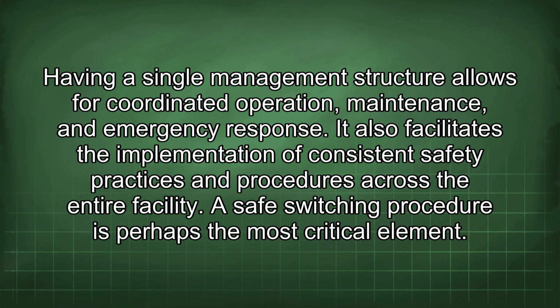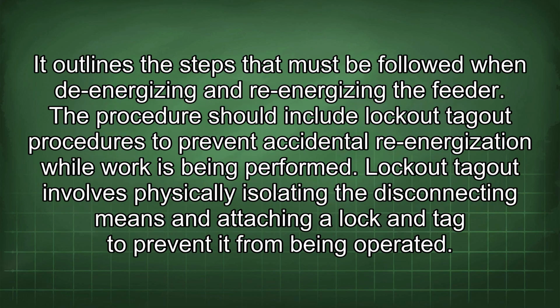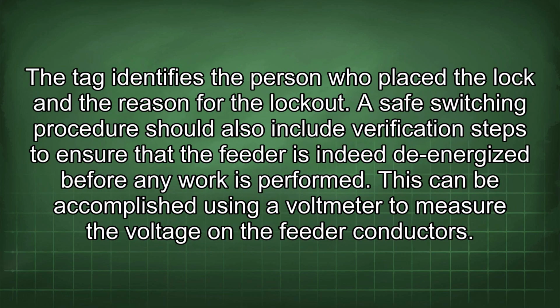A safe switching procedure is perhaps the most critical element. It outlines the steps that must be followed when de-energizing and re-energizing the feeder. The procedure should include lockout-tagout procedures to prevent accidental re-energization while work is being performed. Lockout-tagout involves physically isolating the disconnecting means and attaching a lock and tag to prevent it from being operated. The tag identifies the person who placed the lock and the reason for the lockout. A safe switching procedure should also include verification steps to ensure that the feeder is indeed de-energized before any work is performed. This can be accomplished using a voltmeter to measure the voltage on the feeder conductors.